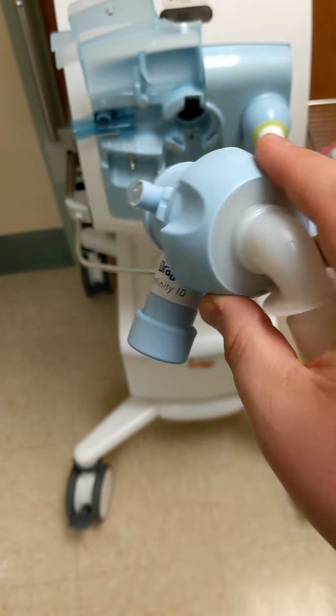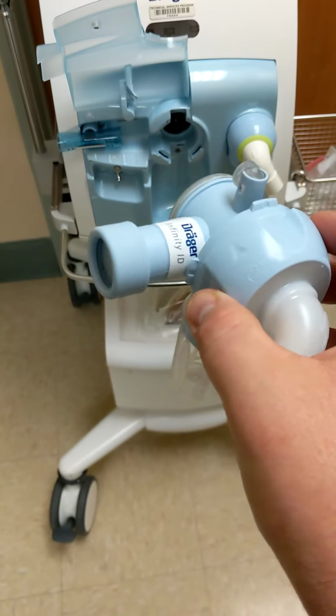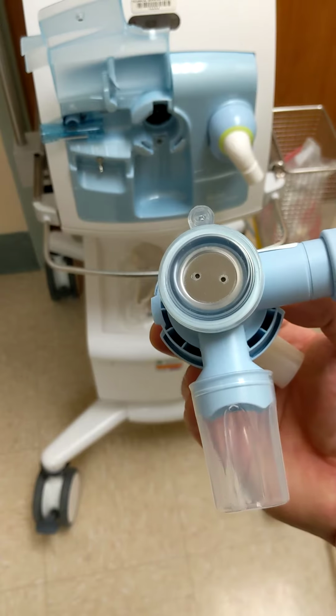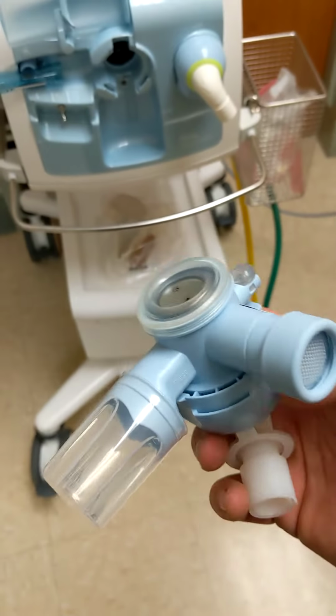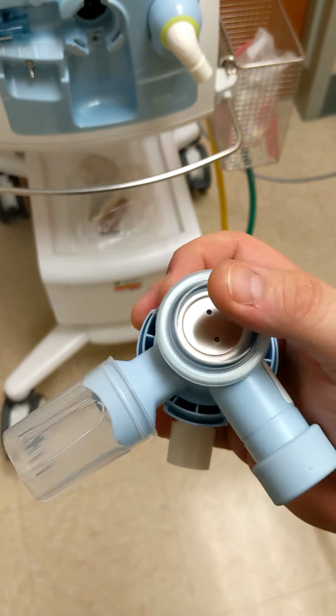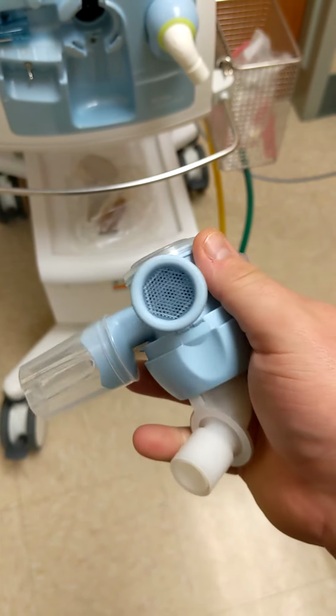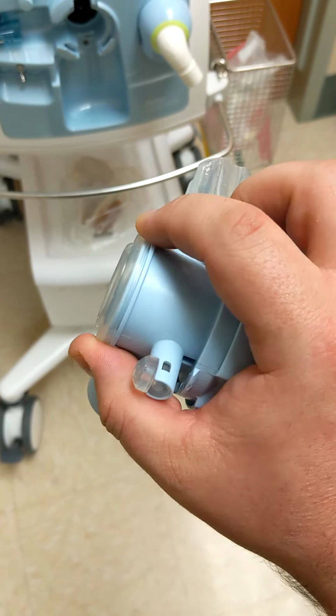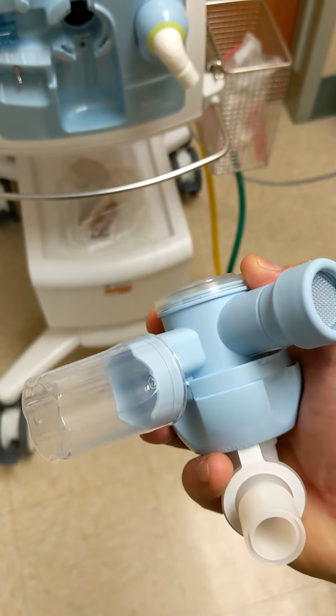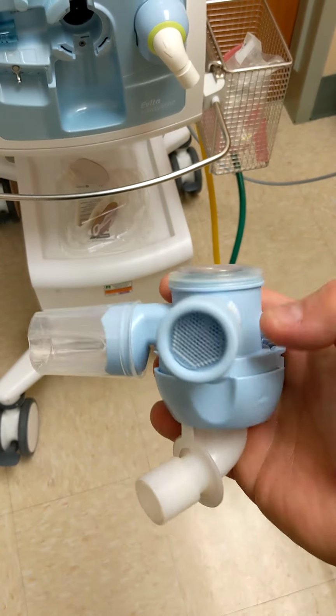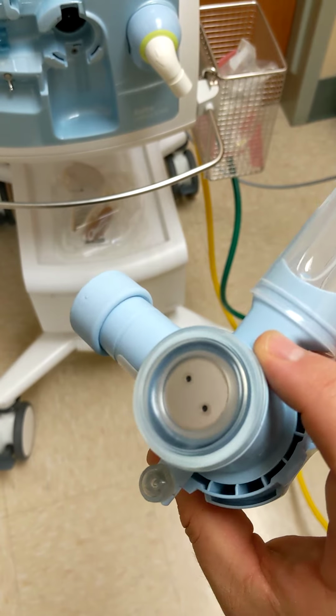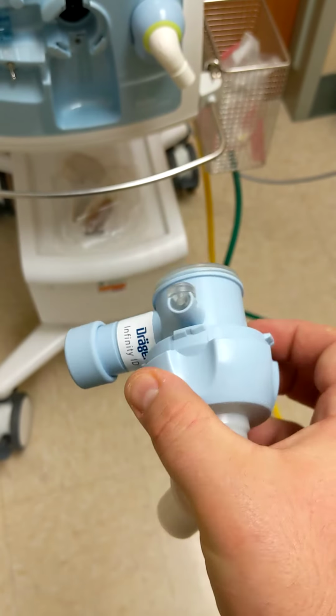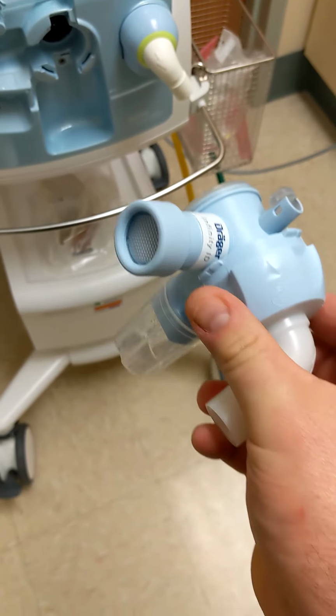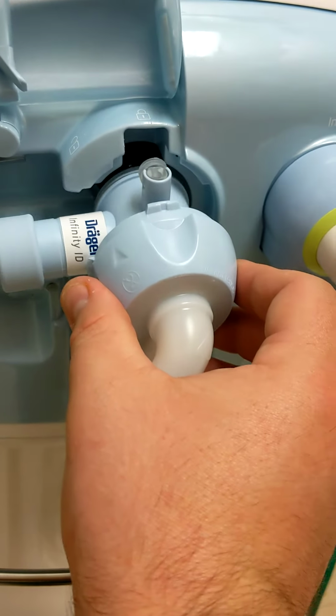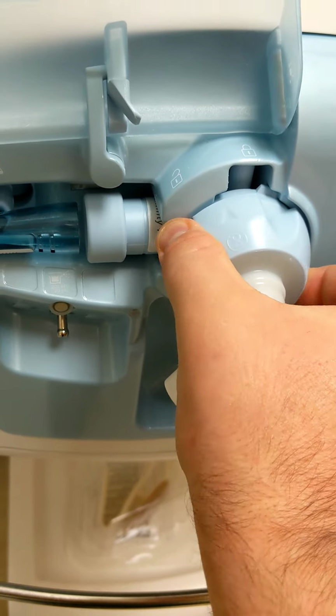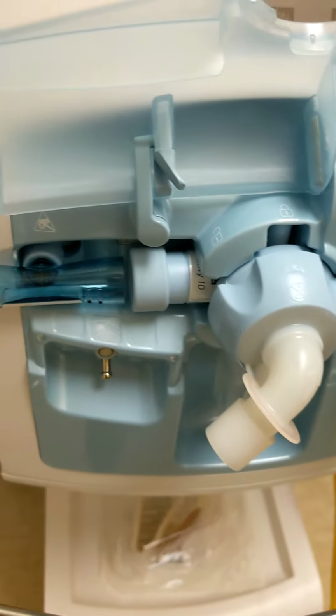The next step will be to put in your exhalation valve. When it comes in the bag, there is this little membrane. This is a very soft membrane, and sometimes it's not seated on correctly. You have to make sure this is seated well. It's not pinched, it's not kinked in any way, and it's on tight. Once you have that done, it inserts very easily, twist, and it locks in.